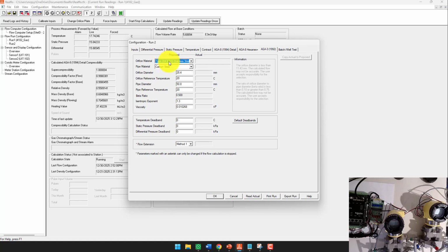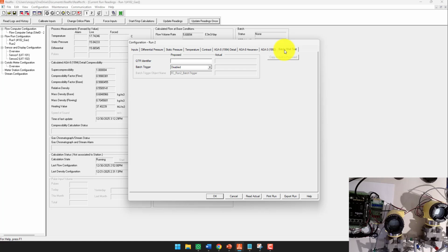We'll go to AGA3. We're going to keep it as stainless steel and carbon steel. The orifice diameter will be the same as the other one, so 25.4. The reference temperature will be 20 degrees. That's what temperature it was when they measured the orifice plate diameter. Pipe diameter will be 50.8. The reference temperature will be 20 again. Everything else will stay the same. Batch well test. We'll leave this disabled for now. I'll create another video to go through batch well testing.